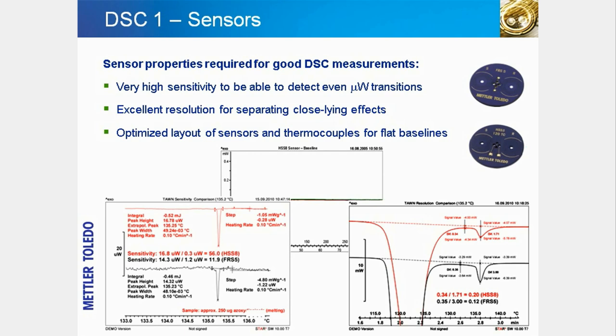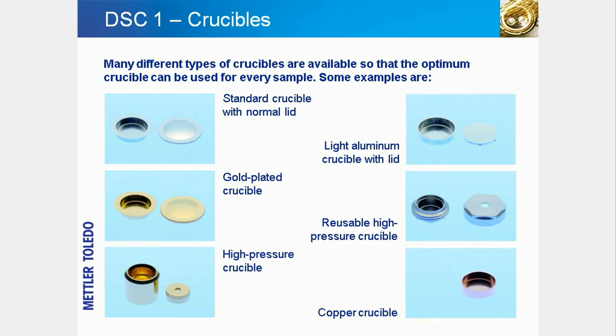Another important performance property in a DSC experiment is the baseline. The baseline should be free of artifacts or drift because effects like these could overlay or hide true sample effects. The diagram in the middle of the slide shows the very good baseline performance for both the DSC-1 sensors, confirming that measurements display real sample effects and not artifacts. For quantitative heat flow measurements, the crucible containing the sample must have excellent thermal conductivity and be in optimum contact with the sensor. Thus, the geometry of the crucible and the material used are very important.